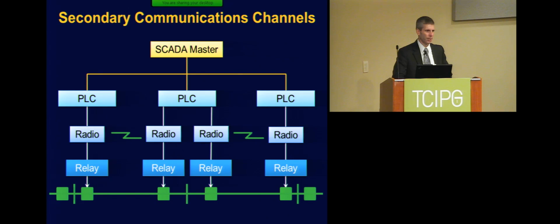We use radios between the substations. Here on the left-hand side, I've got a radio talking to the other relay in the middle substation, sending trip or block information, maybe 1 or 2 bits back and forth. The channel in the radio is usually pretty large, so we have a lot of unused capability inside that radio link. In the normal course of business, the PLCs grab information out of the relays and report it back up to the SCADA master.